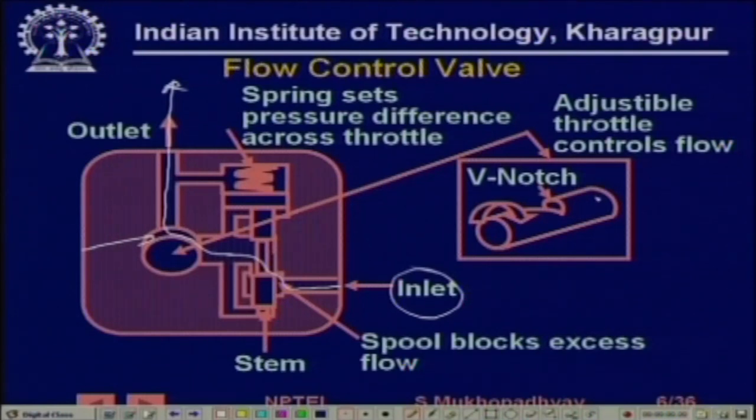It's a cylinder with a V-shaped notch in the middle. Because the notch is V-shaped, if this is rotated, then the ends of the V will come here. This crescent will become like this. Then the fluid has to flow through this much of opening. Right now it is flowing through this much, because the cross section varies: here the cross section is low, here it is more, here it is maximum. So as you rotate it, the cross-sectional area through which the fluid flows can be determined. This is the first thing.